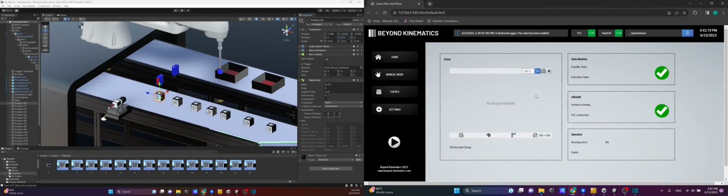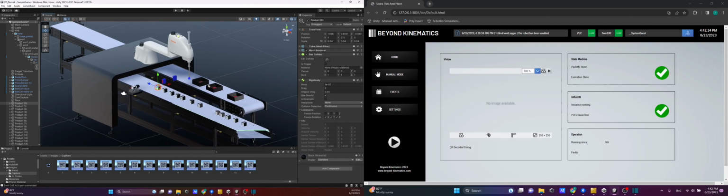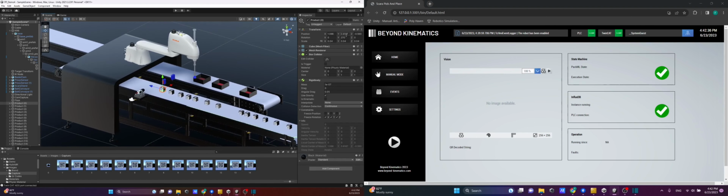Let's demonstrate how to leverage this digital twin to do offline PLC code development. I want to modify the control logic to handle a scenario where the camera cannot read the QR code. If that happens, the robot won't pick the product and the conveyor will index once. Eventually, the ignored product will fall over a reject bin placed by the end of the conveyor. To test that, we can change the orientation of the product so the camera can't see the QR code.